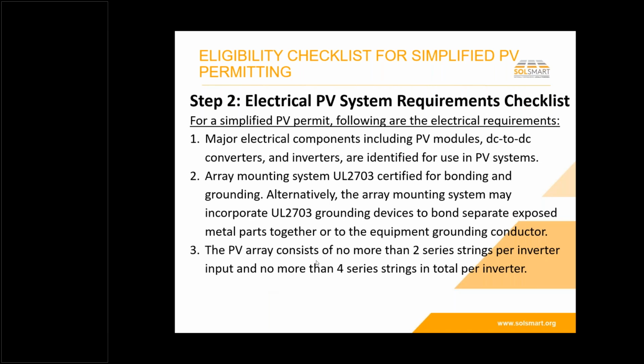And then the array consists of no more than 2 series strings per inverter input. Some inverters have 4 inverter inputs, and so you could do up to 2 strings per input, however, no more than 4 strings total per inverter. And that's the way a lot of systems are being run today. They might have up to 4 strings of modules running into them.